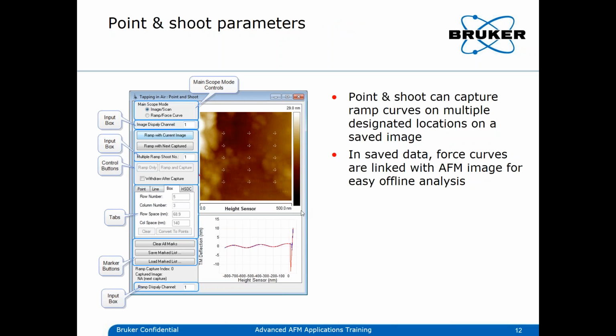Here you can see an overview of the point and shoot parameters. Basically, at first you should obtain an image, and then you can set up the points of interest, either by using a box, like here, where you can have a row of data points, or you can simply select them individually. It depends on you if you just point them or if you convert a box into a grid, into a raster where it would measure each and every point after each other. So point and shoot can capture ramp curves on multiple desired locations, again with various settings here.